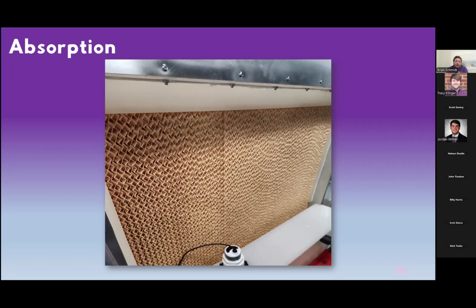The air is flowing through these channels. The air is directly touching the liquid desiccant, so there are no heat exchangers or anything like that. The air is directly touching the liquid desiccant, which again has permeated this pad. As the concentrated liquid desiccant flows down, it is picking up moisture from the environment. It is becoming dilute. We then have a tank at the bottom that catches that diluted desiccant, and we send it to the other side. Here, I'll show you in just a minute. And we're doing the exact opposite process on the other side.